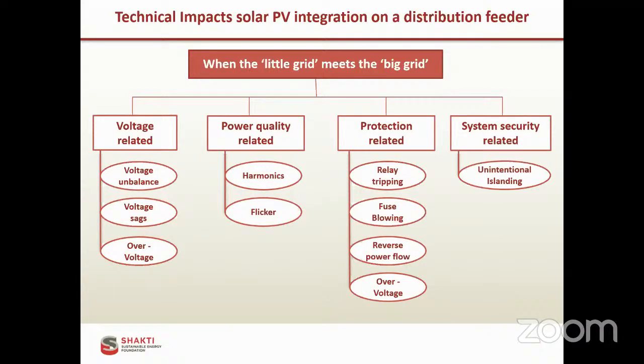In case of past surplus utilities and excess generation from solar rooftop sent back to the grid, it creates reverse flow into the distribution grid, which has long-term impacts on the health of the distribution grid. Another key issue is phase balancing, which arises from the integration of distributed single-phase grid-connected solar rooftop PV.